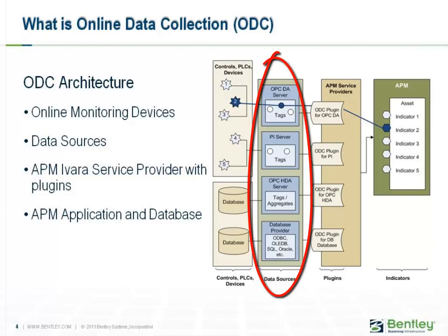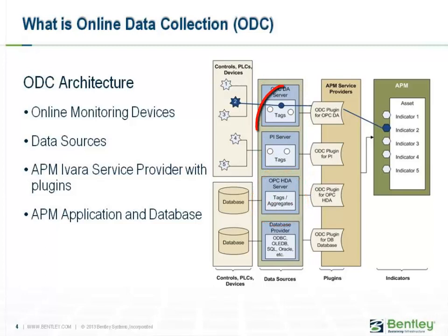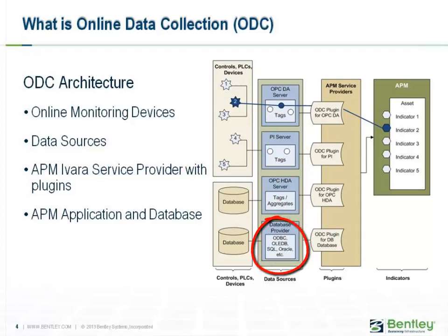The data source is a third-party application provided by the monitoring device manufacturer to expose field data to other applications like APM. It can be an OPC DA server that provides real-time data, an OPC HDA server that provides historical or aggregated data, a PI server which is a Process Historian that can provide both real-time or aggregated data, or any other database or historian provider that supports Open Database Connectivity (ODBC) or Object Linking and Embedding for Databases (OLEDB).